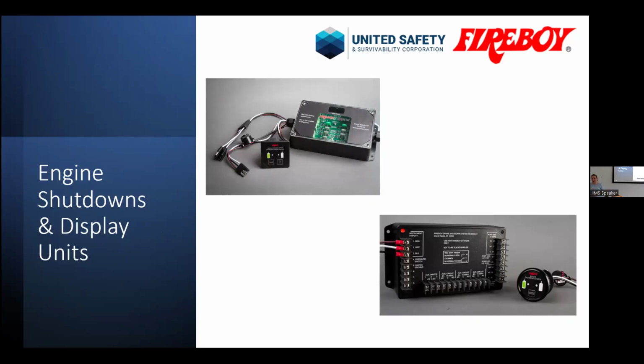And in the instance of fitting an engine shutdown, which is only a requirement if you have an automatic discharge, you have to shut your ventilation and your diesel engines prior to discharge. It's not required for petrol boats, only for diesel boats, but you then have to have a function of an override, because if it's a false alarm, you still have to be able to start your engines following either a low pressure alarm or a discharge of the extinguisher and get back to port if you were outside in the sea, or just to make sure you can keep going while you refill your cylinder or troubleshoot the fault.